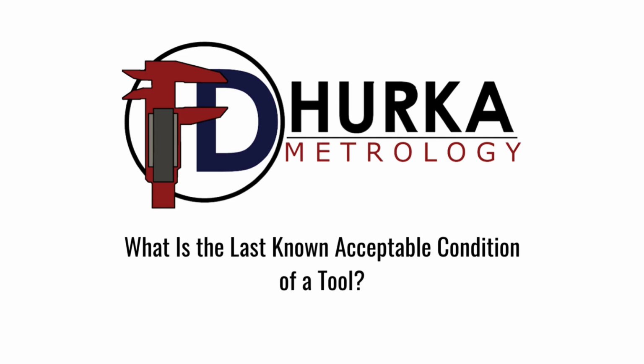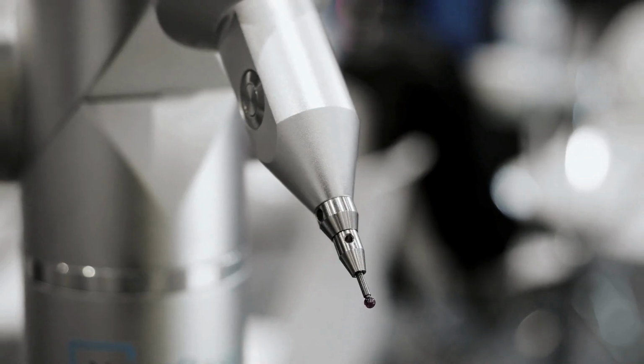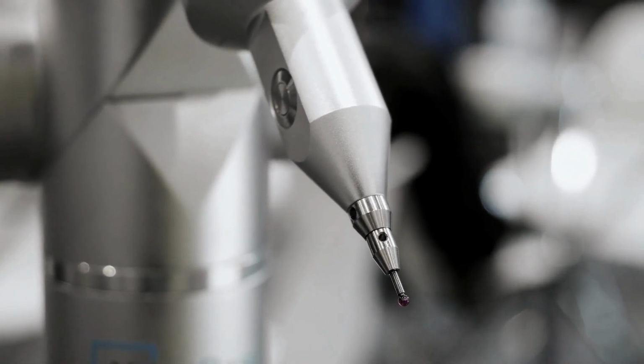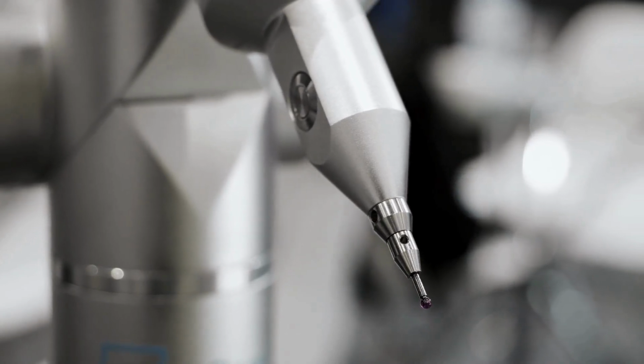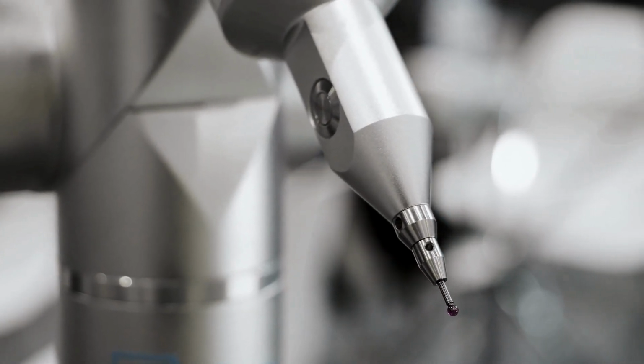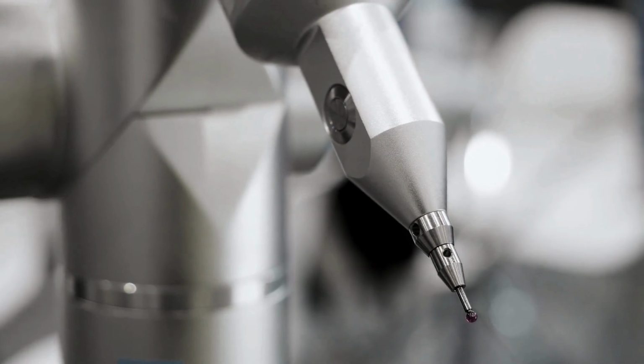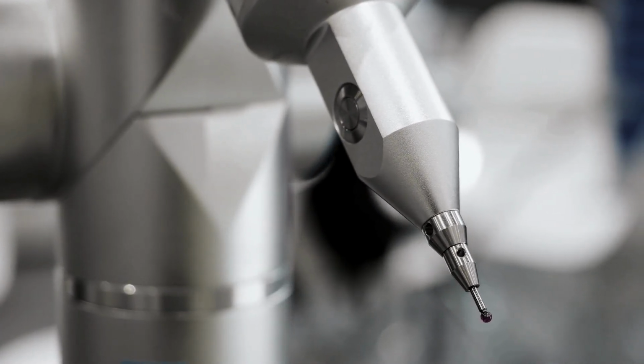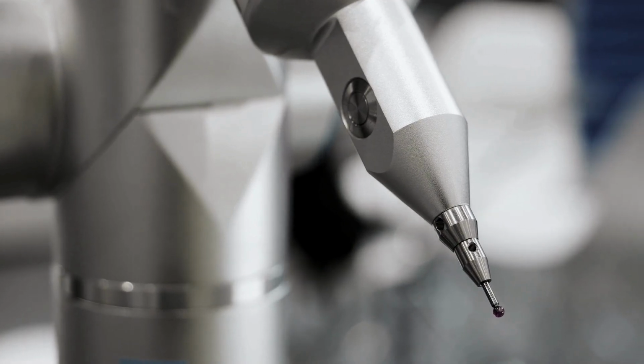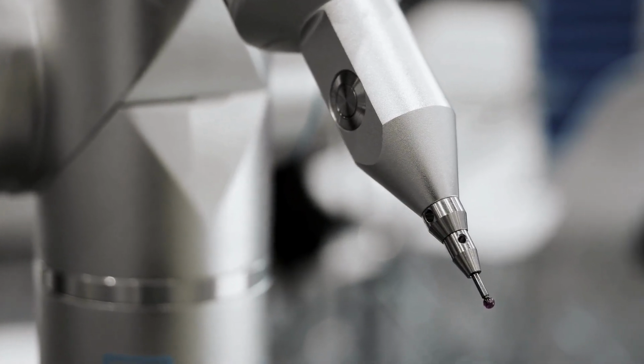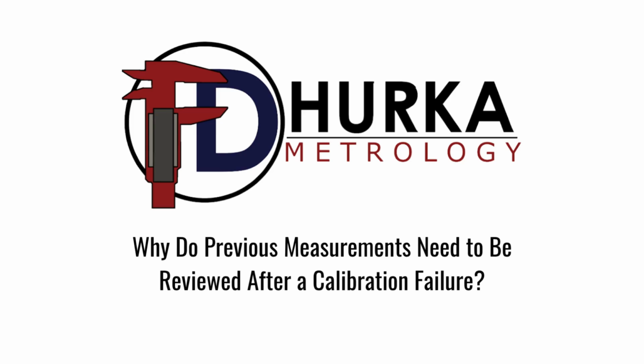What is the last known acceptable condition of a tool? It is the most recent point at which there is evidence the tool was performing acceptably. This may be the previous successful calibration date or other proof, such as interim checks, verification data, or control chart results. Why do previous measurements need to be reviewed after a calibration failure?